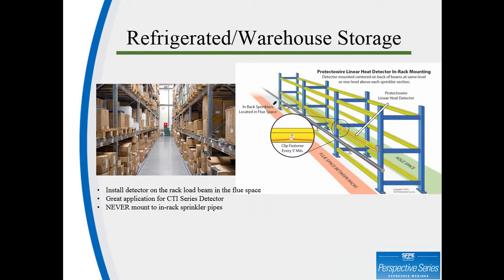Refrigerated and warehouse storage is another popular application for digital linear heat detection. For this application, we typically recommend a hybrid system. Standard digital linear heat detection, where the conductors are the same metal, can be used in the ceiling. For any and all rack installations, we recommend our CTI Series detector. Any detector installed within a rack has a higher risk of damage. With our CTI detector, damage will only initiate a trouble condition, not an alarm. The detector should be located on the back of the load beam, hidden from forklifts if and when possible.